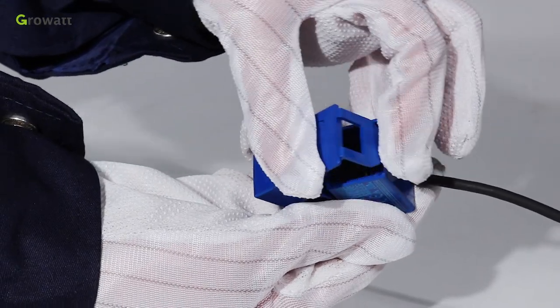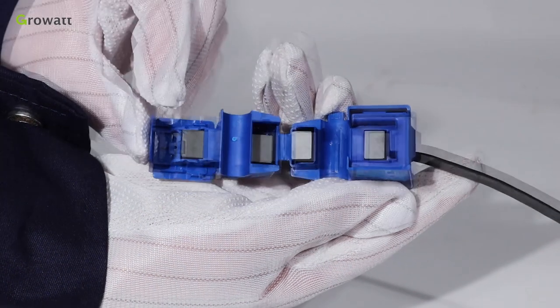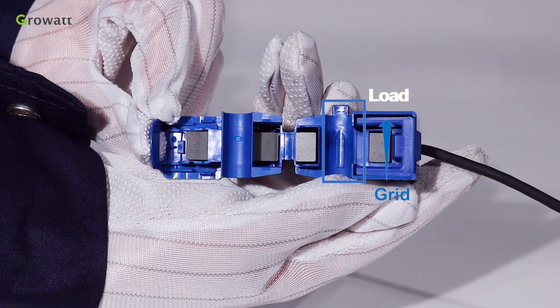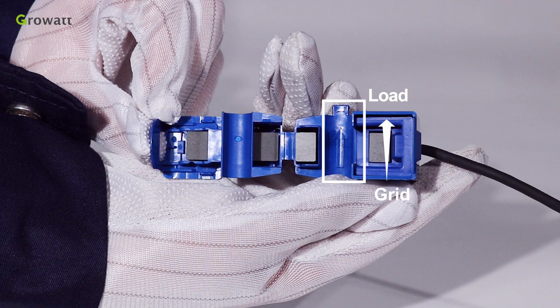Pay attention to the direction of the CT as illustrated. Open the current transformer and you can see an arrow labeled on it, which indicates the current direction. The direction of the arrow means from public grid to user load.